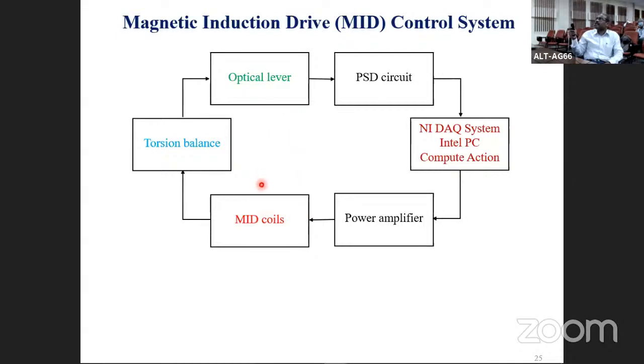I am not going to go into details of this thing, but your torsion balance, whose motion is monitored by optical lever, a PSD circuit is used for measuring the angle. That information goes to a computer which computes the action, in which direction, at what time, and how much to apply the drive, which goes to the power amplifier. Power amplifier drives the coils and which controls the torsion balance.